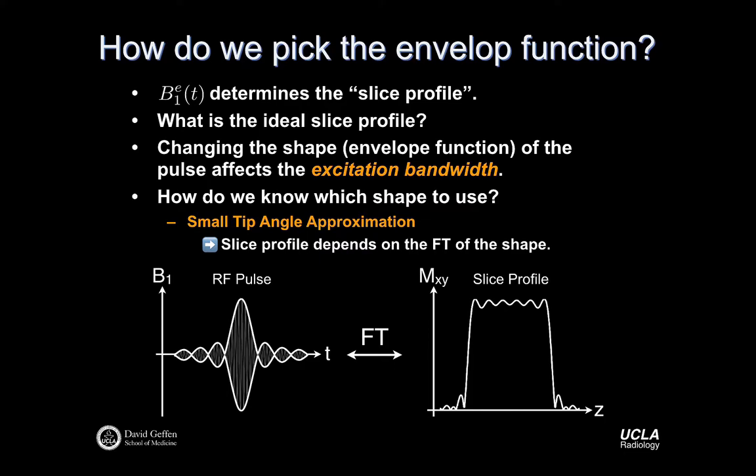What does it mean? Well, I probably should have put some dashed lines on here, which would represent the ideal slice profile. Ideal slice profile would be uniform excitation from the beginning of the slice to the end of the slice, right? In this example, let's assume that the target slice thickness is maybe close to this minimum, just to keep us on the same page. What it means is that at the very edges of the slice, we have very little excitation, and then pretty quickly it rises to the target level of excitation.